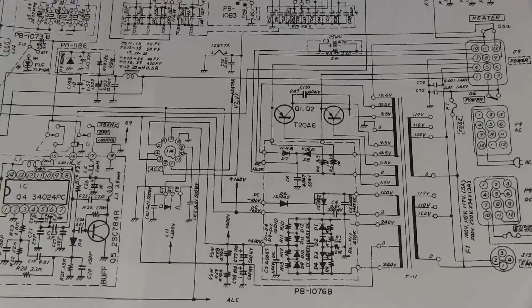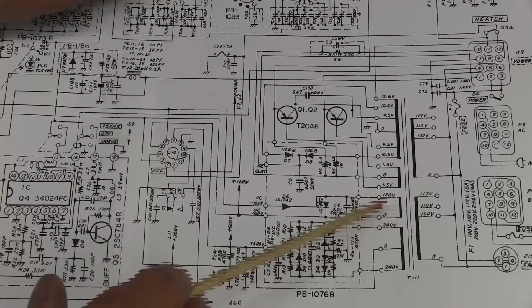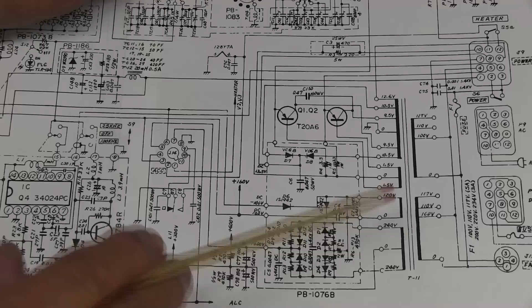So back to our schematic. There's our 160 volts out of the rectifier board. And see it comes here and it goes up and says 160 plus, and then it takes off and goes somewhere else. But if we trace this back, we're going to see there's one diode across it, and we trace back, we can see that 120 volt lead. So we should have about 35 to 45 ohms from that 120 volts to 0, and that'll tell us the condition of this winding in this transformer.